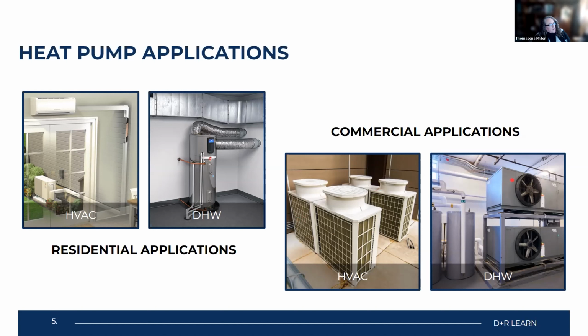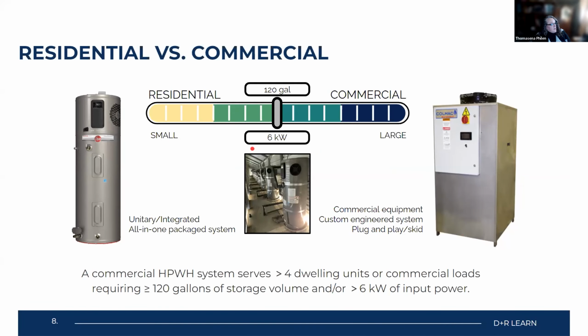But over here, you've got pure commercial heat pump water heating. And so we've got the heat pumps here. They're quite large. We have our storage tanks here as well. Now, if you wanted to get into the nuts and bolts difference between what's considered a residential heat pump water heater and what's considered a commercial heat pump water heater, and there's a lot of wiggle room in the middle too for those things, residential is considered up to 120 gallons. Now, if I'm going to serve more than 4 dwelling units, that goes into the commercial category. If I'm going to be having 6 kilowatts or more of input power, that also goes into the commercial category, as well as anything over 120 gallons of water storage.